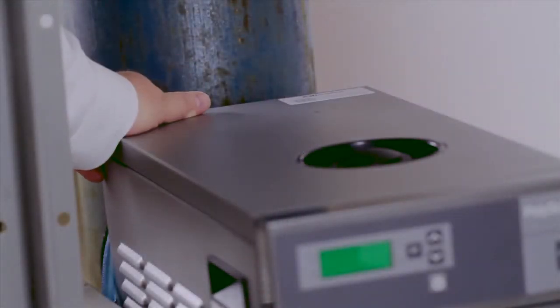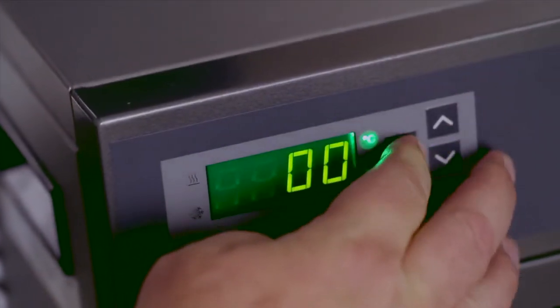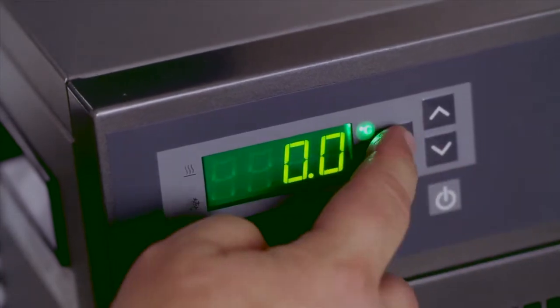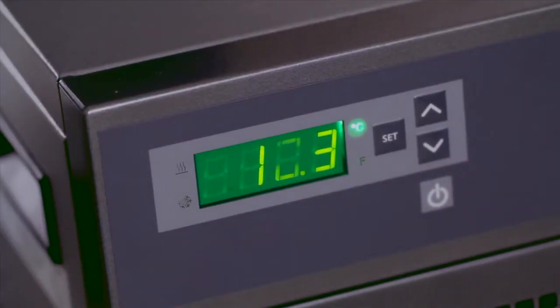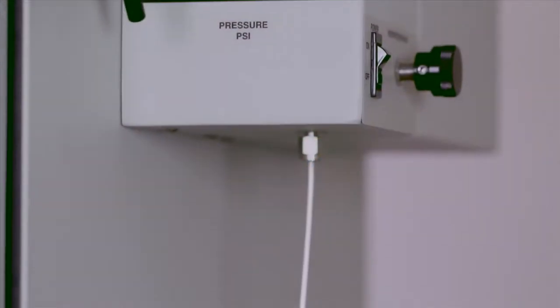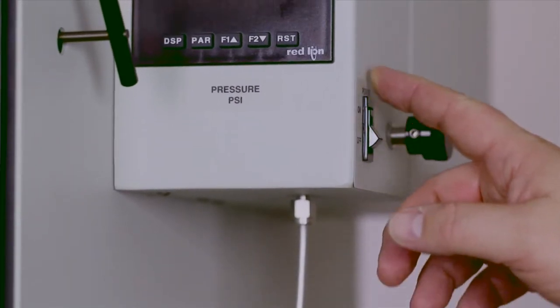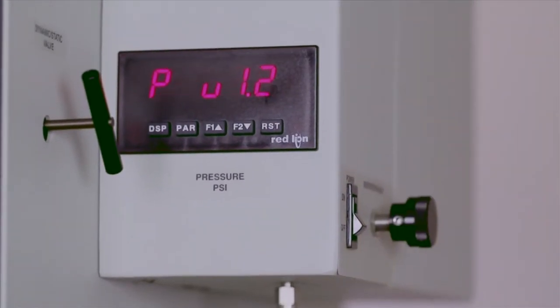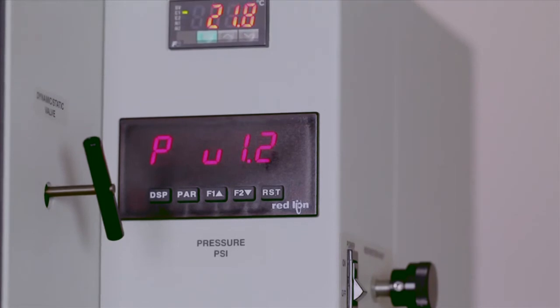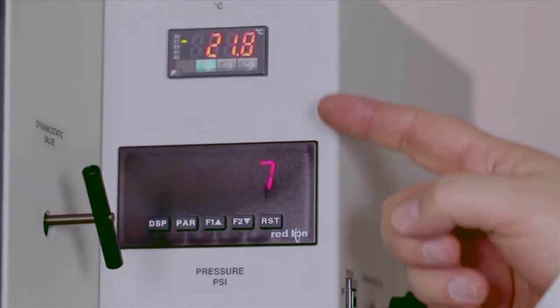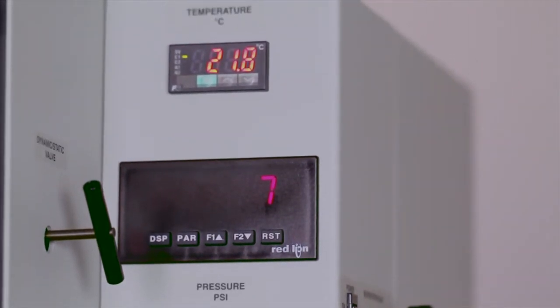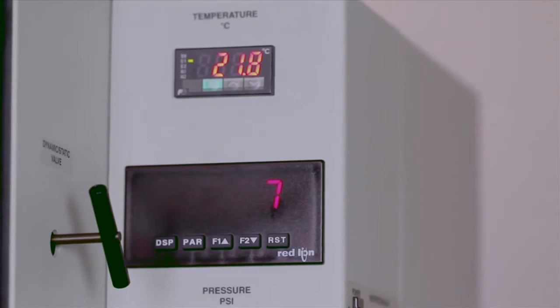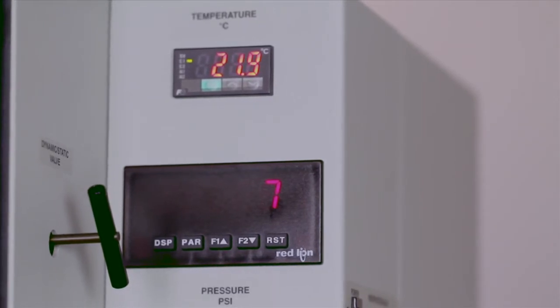Turn on the chiller and ensure that the chiller is set between -5 and 0 degrees Celsius. Wait at least 30 minutes before proceeding to the next step. After 30 minutes, turn on the main power switch to the SFT-150 located near the restrictor assembly. Within a few seconds, the controller's LED panel near the restrictor assembly will display the system's current parameters. These will indicate ambient conditions.